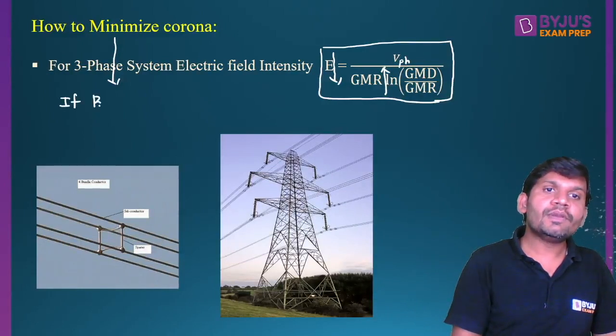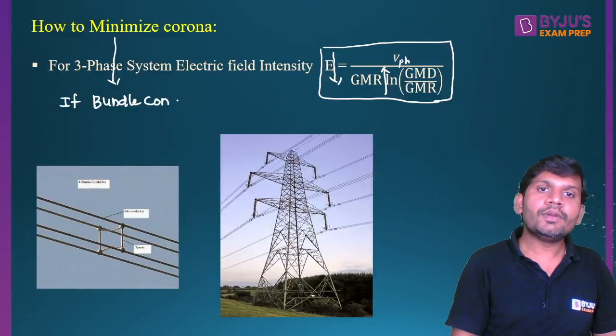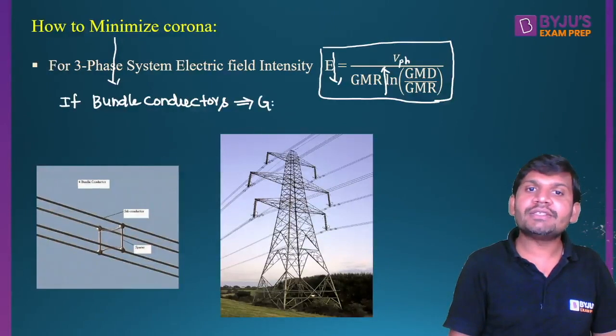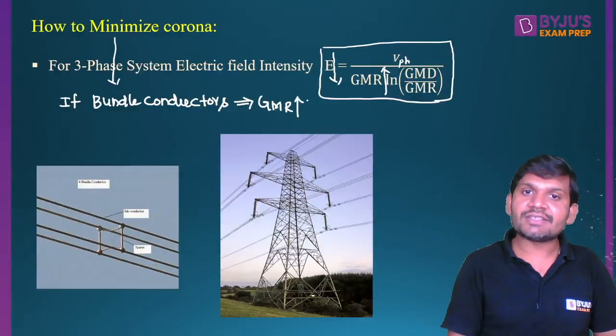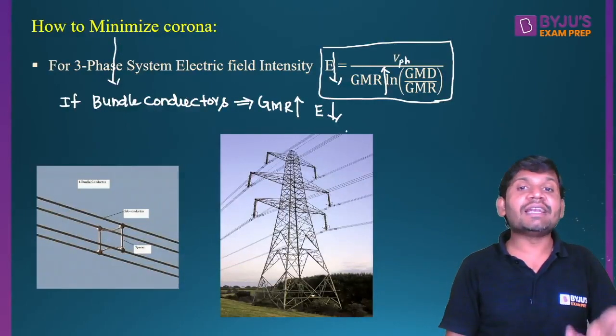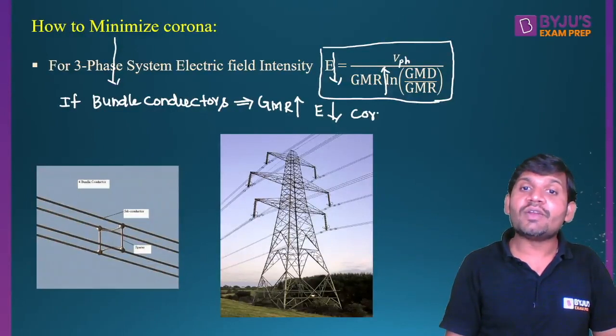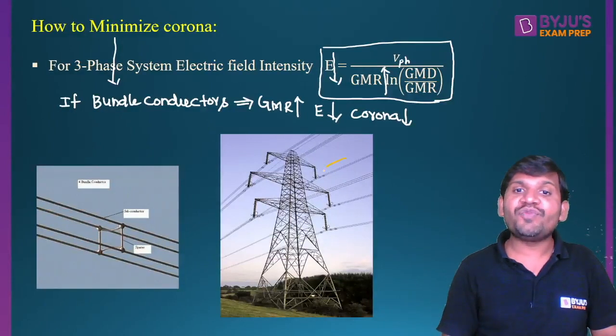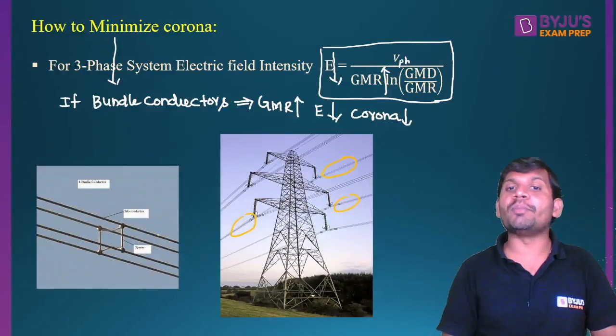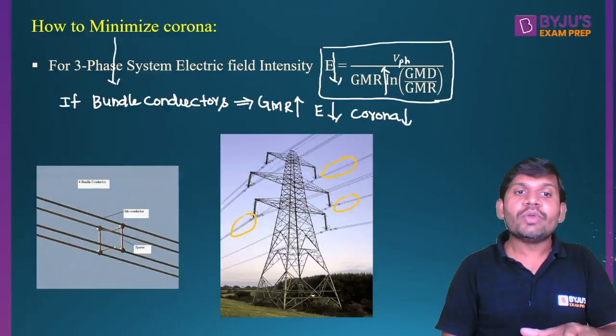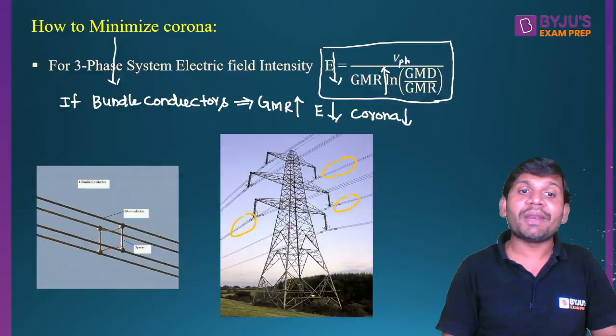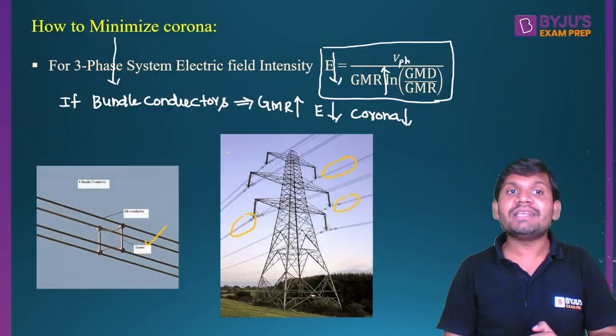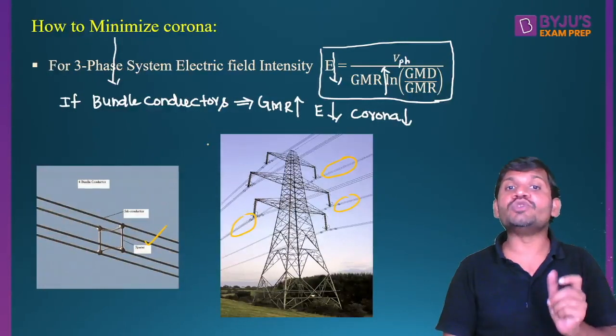If bundle conductors are used, the GMR (geometric mean radius) is increased. When the GMR is increased, the electric field intensity is reduced. When the electric field intensity is reduced, the corona effect is reduced. Bundle conductors means per phase we are using more number of conductors. Here we are using four conductors per phase, and these conductors are separated by using a spacer — which is a metal link. By using the spacer, we separate the conductors. In this way, we can minimize the corona effect.